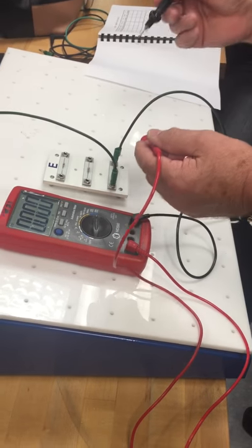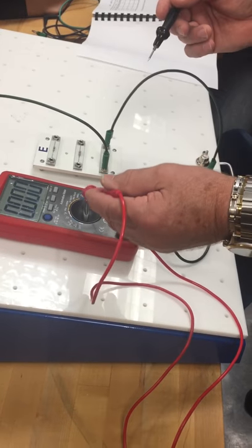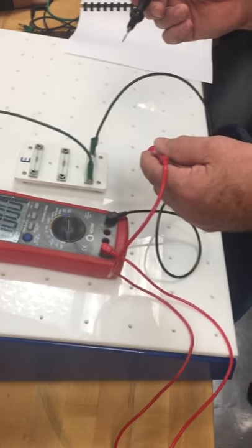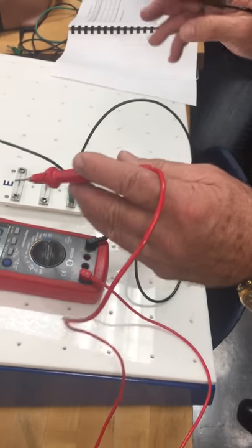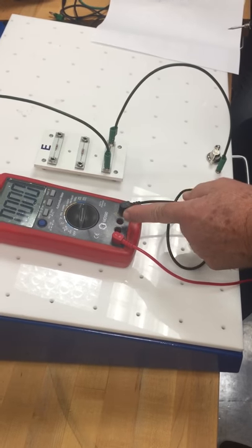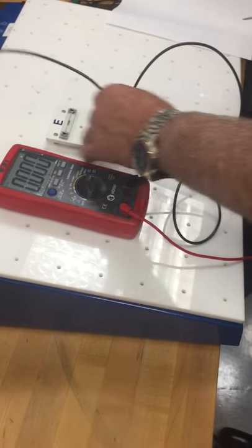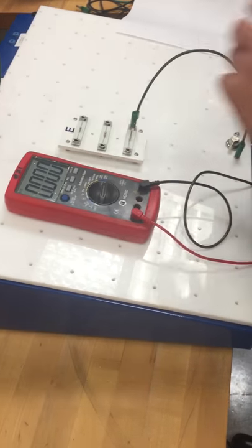So it's shorting it out, shorts the fuse and burns it up. Don't do it that way. When you do this, it has to be on volts and this has to be in the volt port. If you're doing amperage, one of them has to be disconnected and put the red lead towards the positive, black lead towards the ground side.